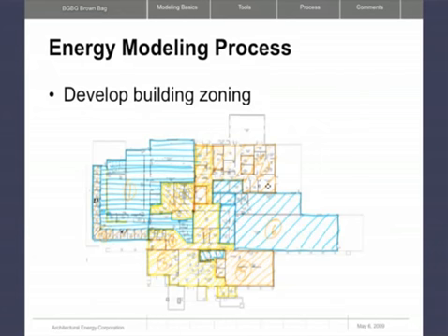In these areas, you have different internal loads, you have different system types for your offices and your front areas, and so the systems will be performed differently, so you want to treat those separately. And then these back areas, again, you have different internal load characteristics, and so those are zoned differently as well.